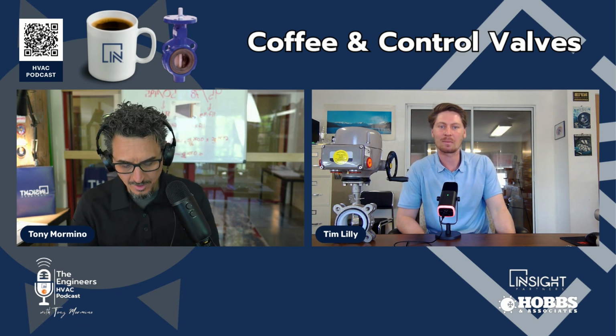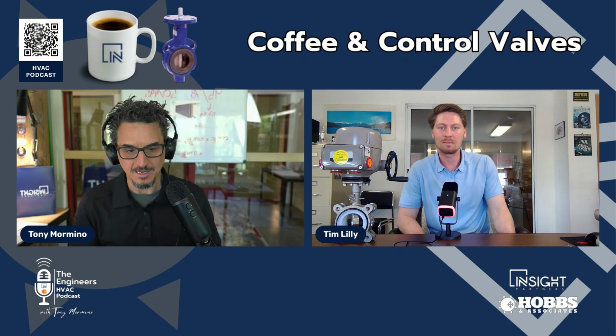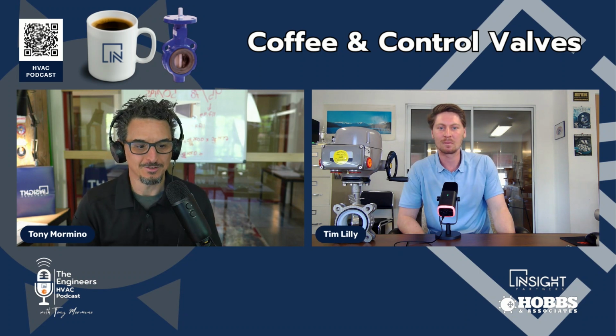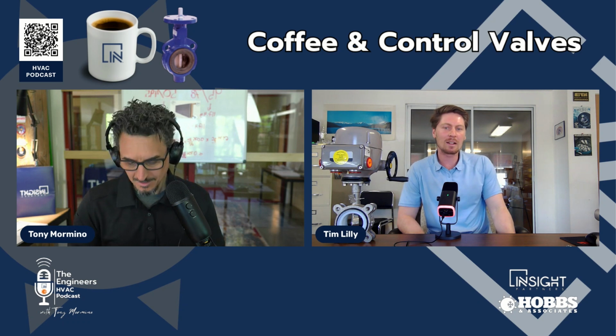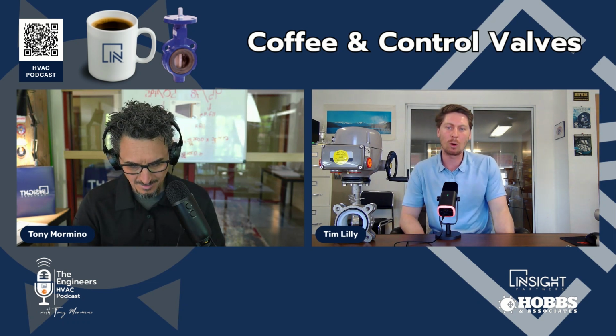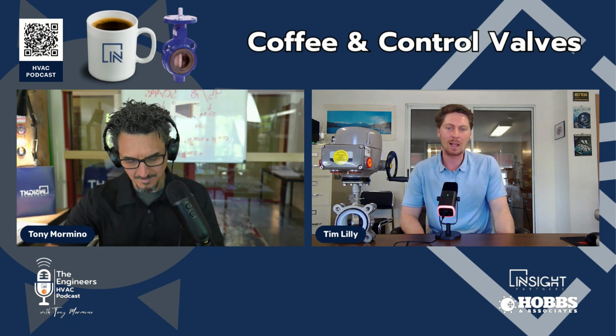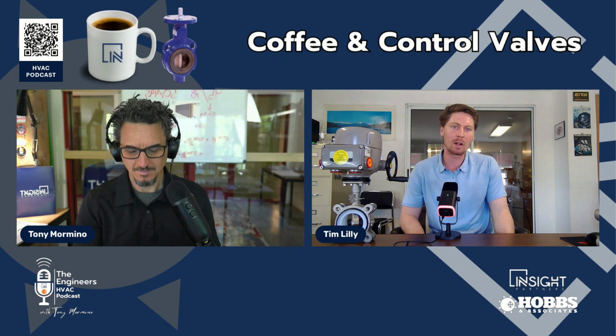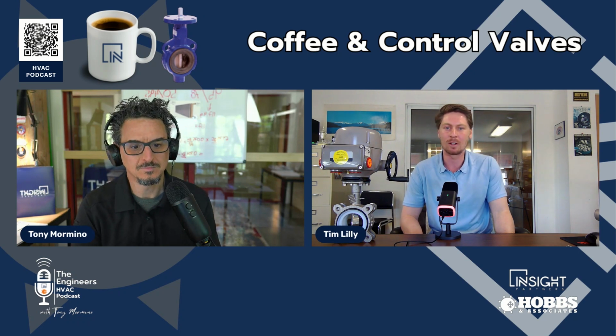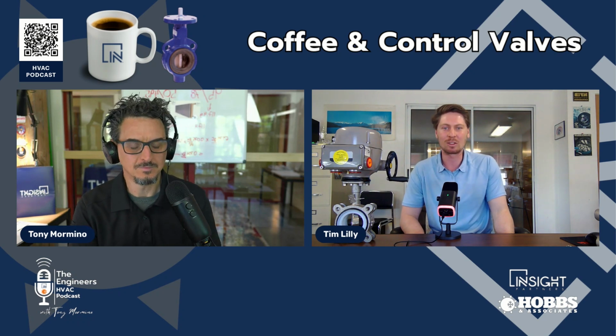Okay. What are the best practices for maintaining chilled water and hot water valves? Is there a lot of maintenance involved in valves? There's not, and most of the butterfly valves are what they call throwaway valves. I quoted an 8-inch butterfly valve yesterday for $800. And so it's not worth your time to go maintain it and buy a repair kit and fix it.